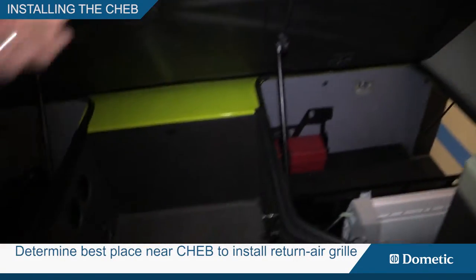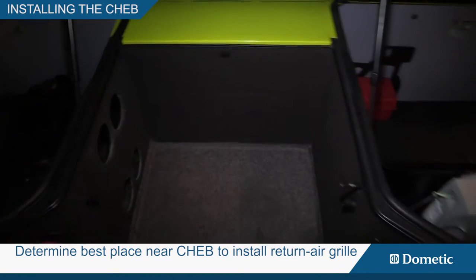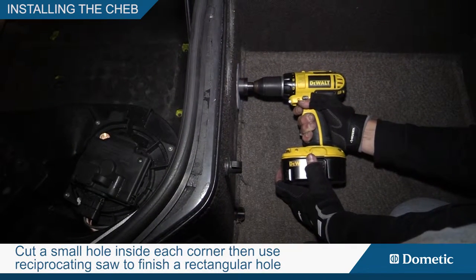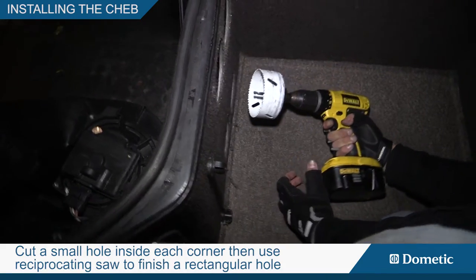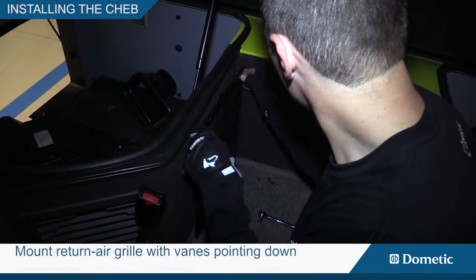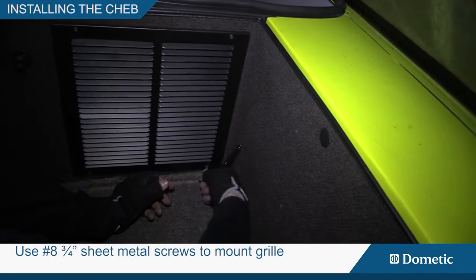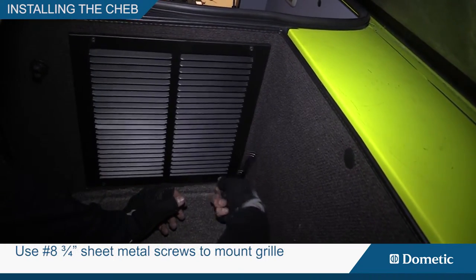Determine the best place near the CHEB location to install the return air grill. Make sure there are no cables or electrical connections behind the panel. Then measure for a hole 12.5 inches by 5.5 inches, or 318 millimeters by 140 millimeters. Cut a small hole inside each corner, then use a reciprocating saw to finish the rectangular hole. Mount the return air grill with vanes pointing down, using number eight 3/4 inch sheet metal screws.